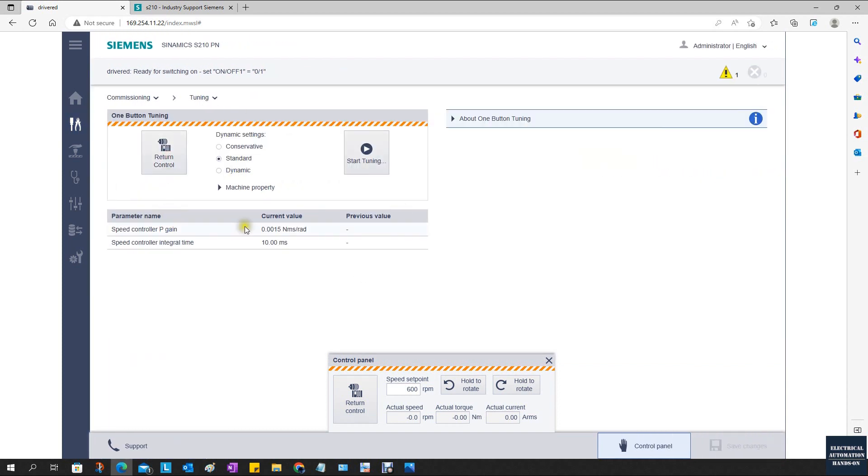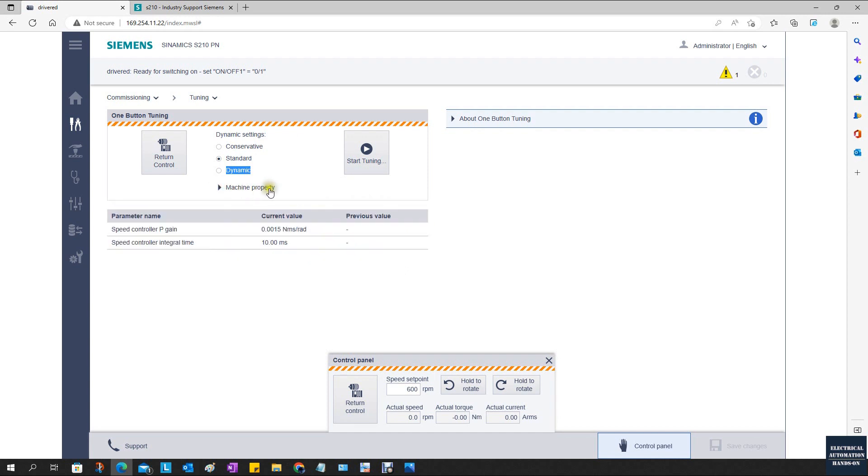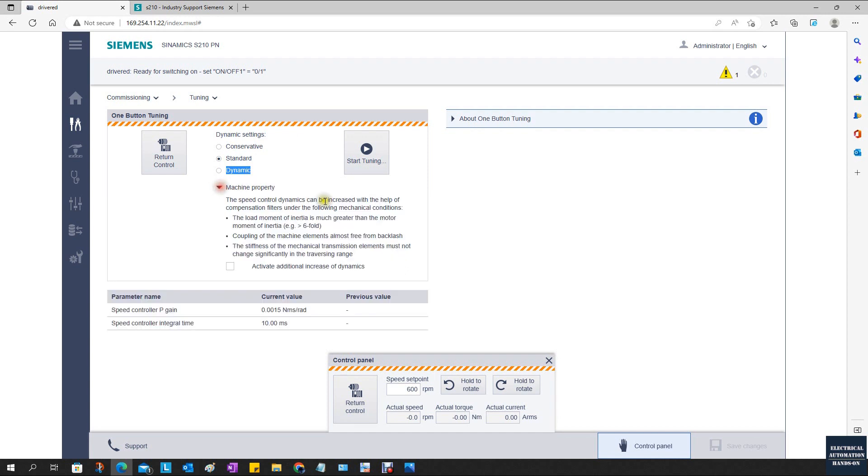From this button here we see three selections: conservative, standard, and dynamic. From the machine property, we can also activate this additional increase of dynamics. In most cases, if your servo drive moves very slow or needs very accurate positioning, you can select standard or conservative.